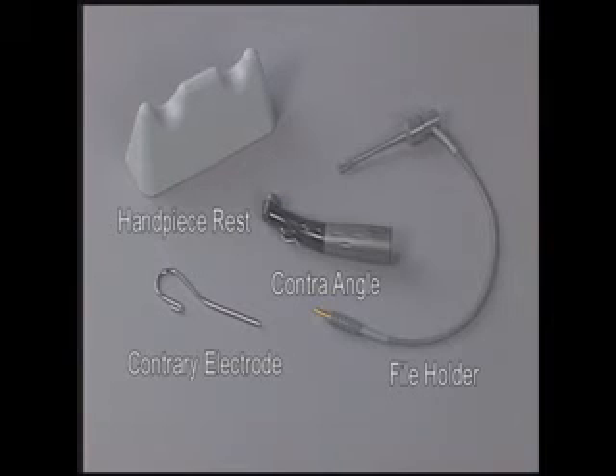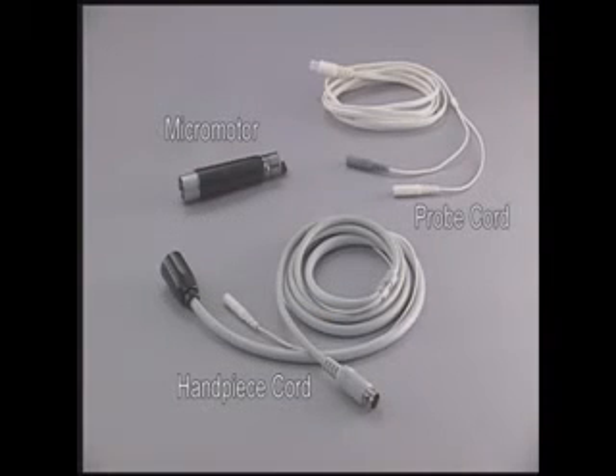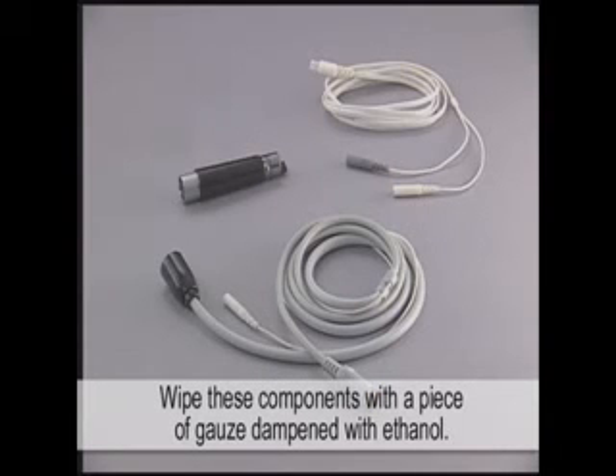The contra angle, file holder, contrary electrode, and handpiece rest can be autoclaved under the temperature of 135 degrees Celsius or 275 degrees Fahrenheit. Thoroughly clean and wash the components before autoclaving. The micromotor, handpiece cord, and probe cord cannot be autoclaved. Wipe these components with a piece of gauze dampened with ethanol.